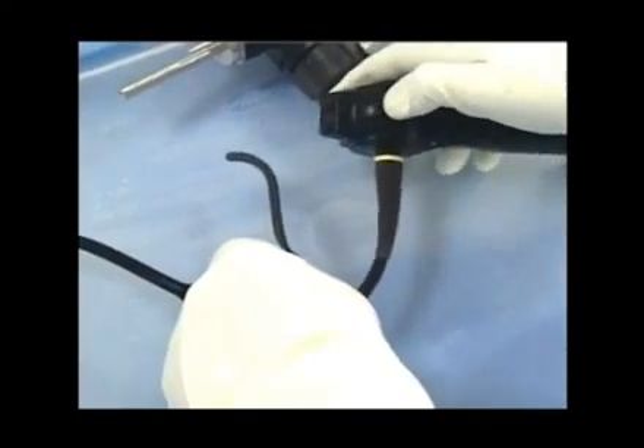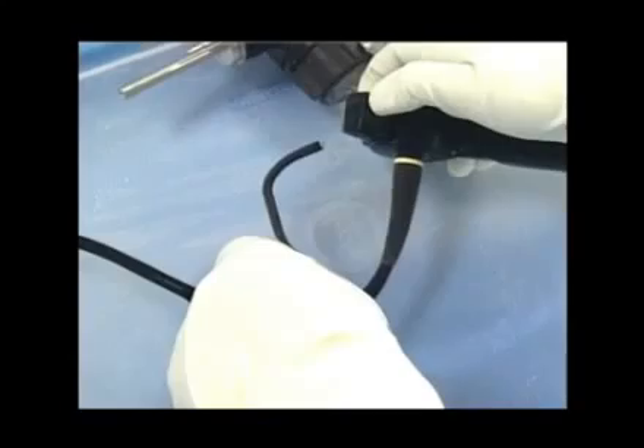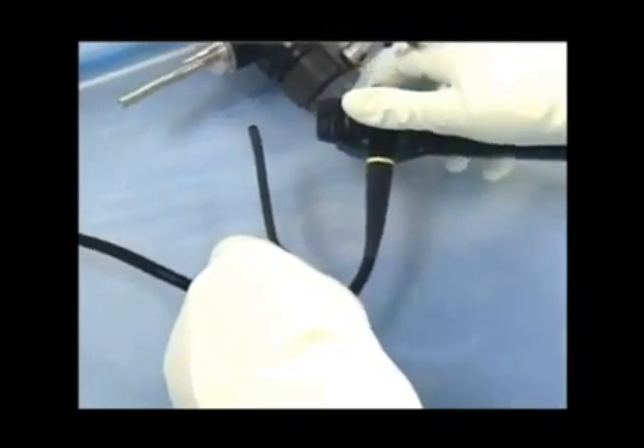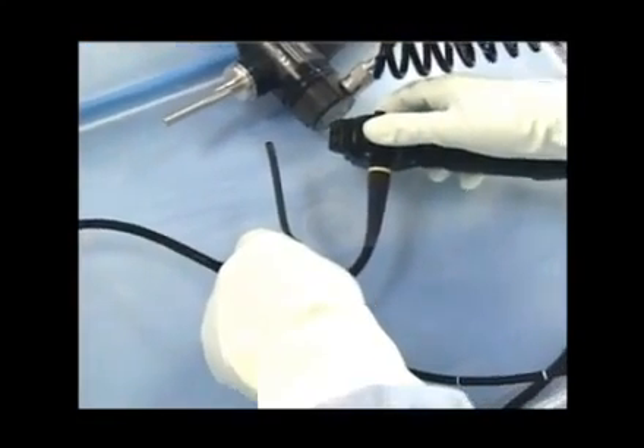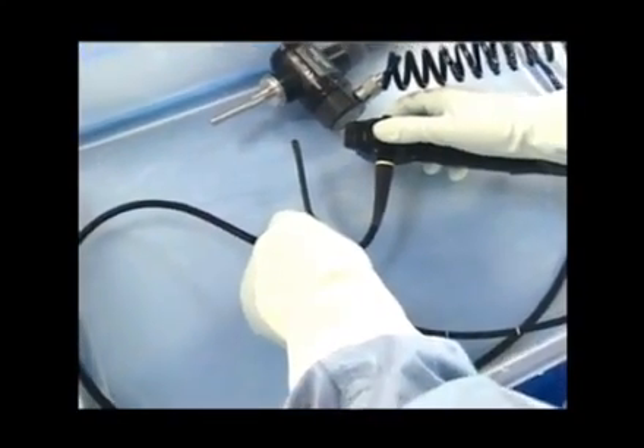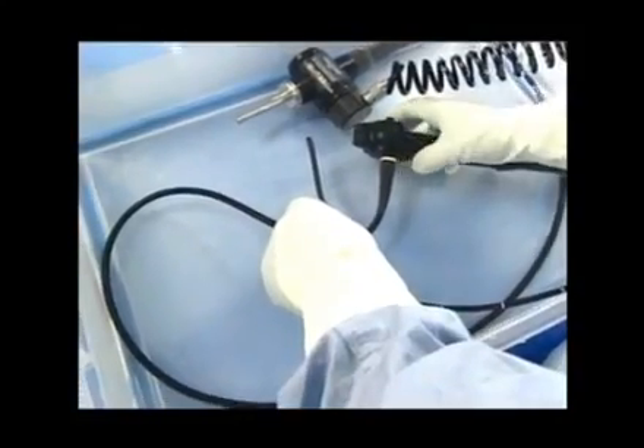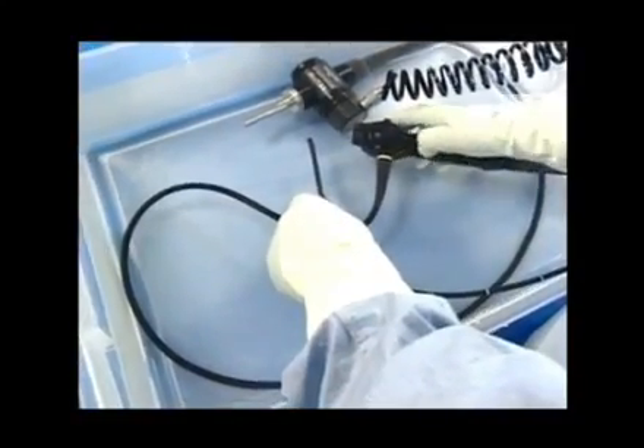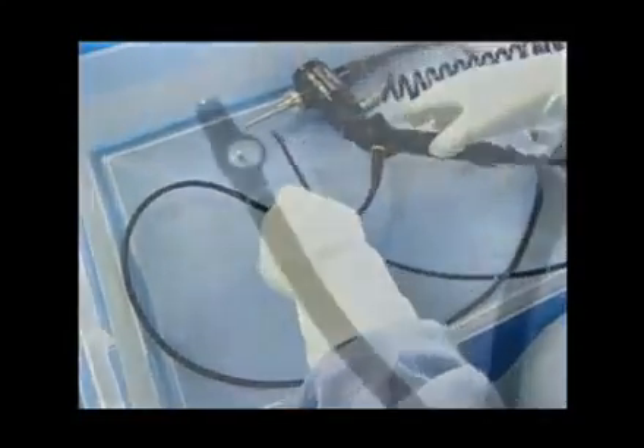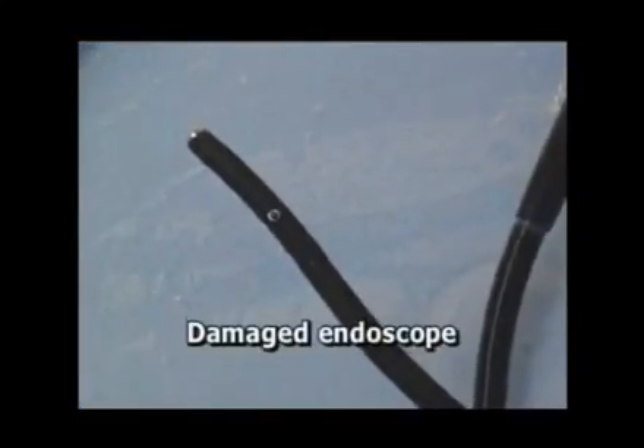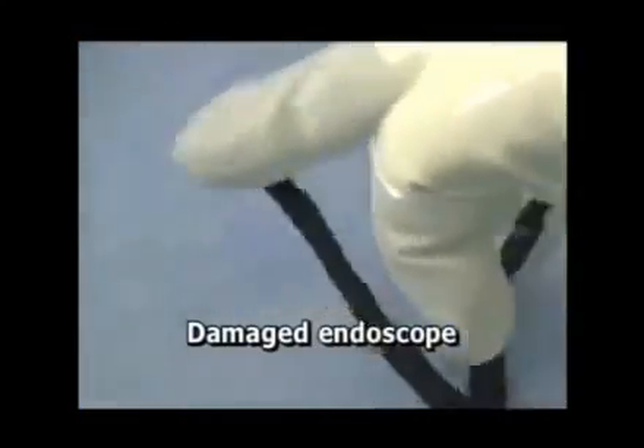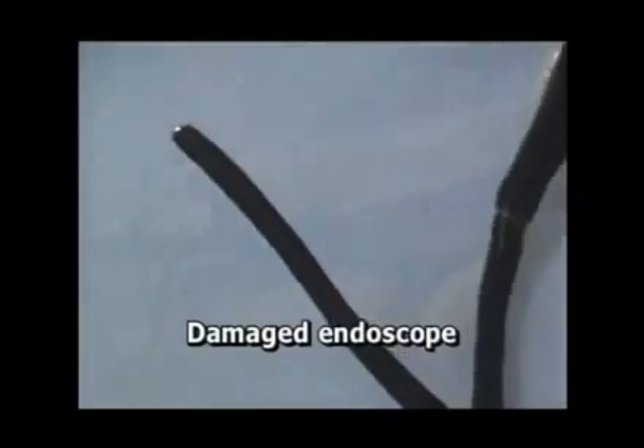Initially, you may see a few bubbles clinging to the insertion tube or coming out of a channel opening. These do not indicate a leak. Wipe away any bubbles clinging to the instrument. If you see no source of continuous bubbles, the bronchoscope is air and fluid tight. In contrast, if you do observe a continuous stream of bubbles, the bronchoscope is leaking.